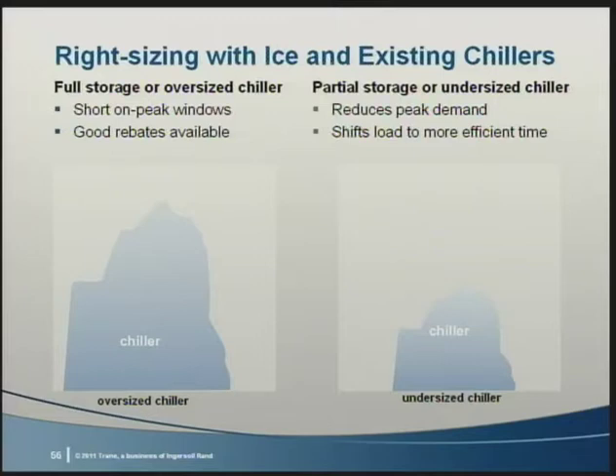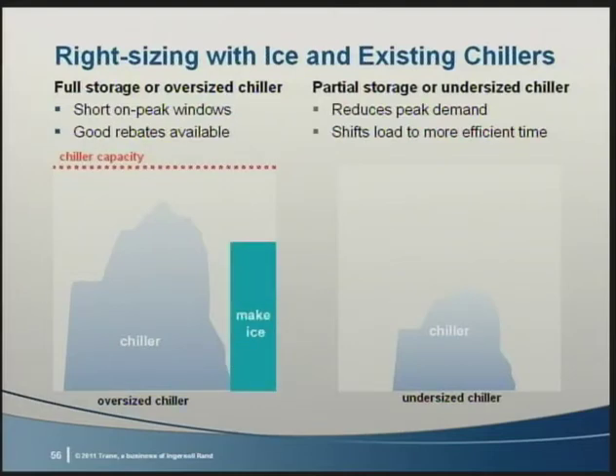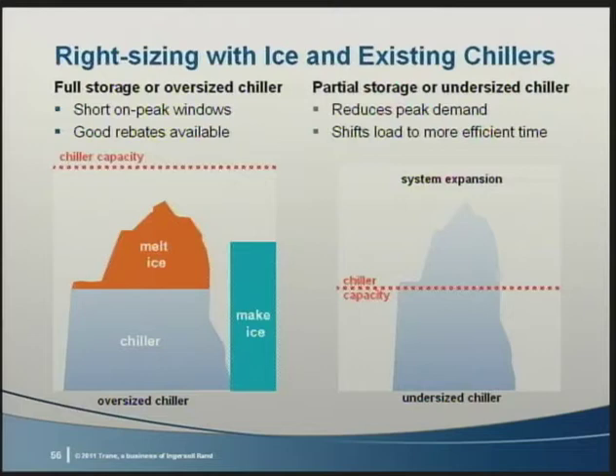If your building has too big of a chiller today, you may be able to completely avoid the on-peak window, since you can make a lot of ice at night if you get enough tanks. Since the oversized chiller is a sunk cost, a few more tanks, especially where rebates or other incentives are available, can be a real game changer when considering full storage. Or simply use the added capacity of the oversized chiller to shed more of the expensive electricity, whether on-peak or demand-related charges.